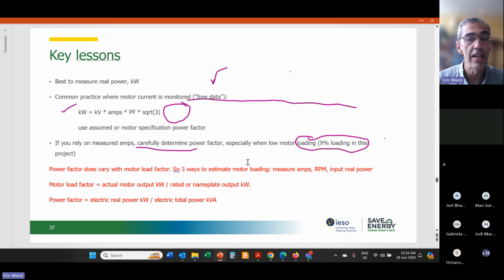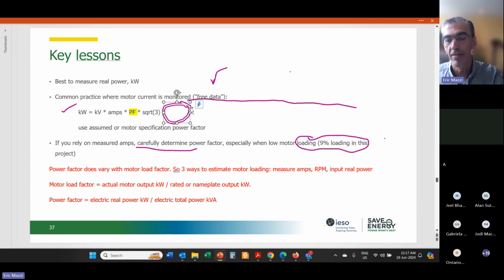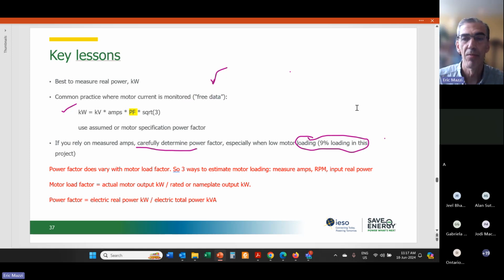Yeah, so again, the key thing here is motor amps are often readily available, and you really want to get real power, and then it's very easy to assume a power factor and estimate your real power. But in this case, somebody got bitten, if you will, because the power factor was severely misestimated, so the real power was really misestimated.